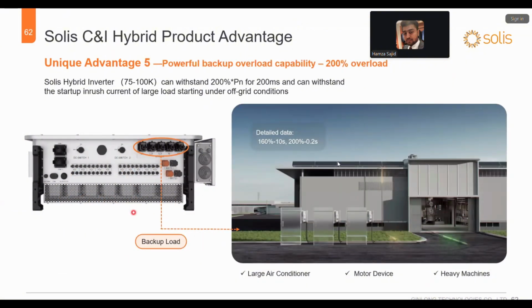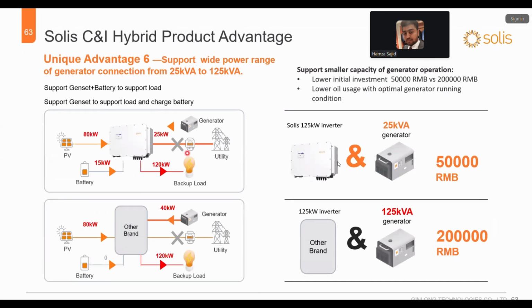This inverter also has the backup port, and it can be 160% overloaded for 10 seconds and 200% overloaded for 0.2 seconds. So the minimum generator you can attach with this one is 25 kilowatt. So collectively, if PV support of 80 kilowatt is available, it can discharge the battery for 15 kilowatt, and it can support a load of 120 kilowatt. But with other brands, you have to go with the same size generator, and the price difference between 25 kVA and 125 kVA is huge. So for applications where customers need an uninterrupted supply system, if they want to add a generator, they can easily choose a small generator to work with the system.